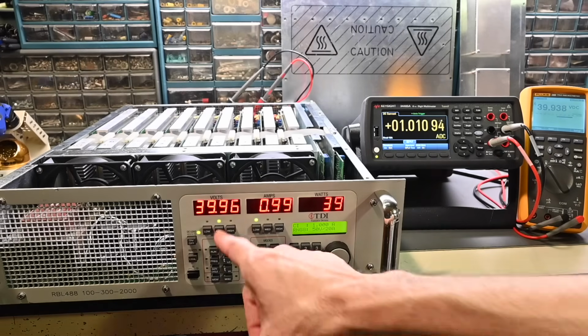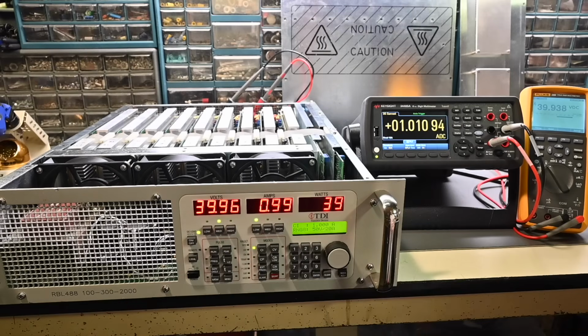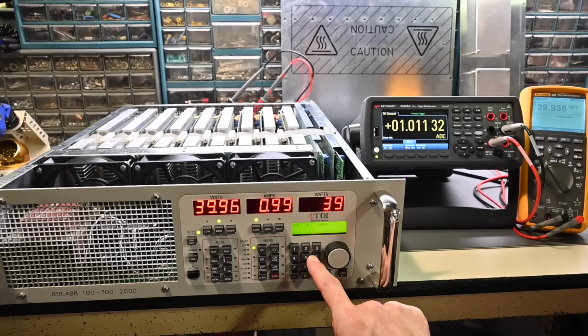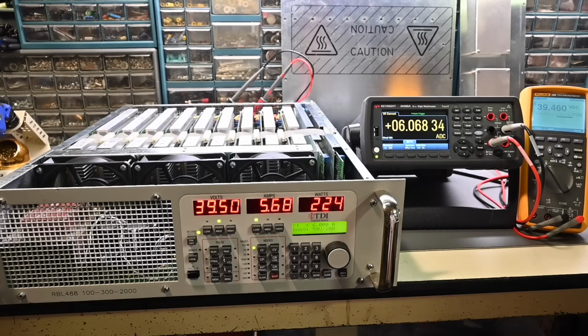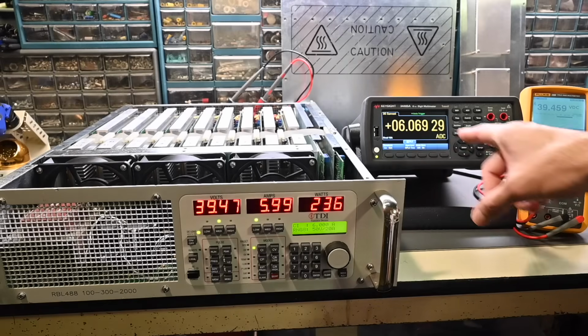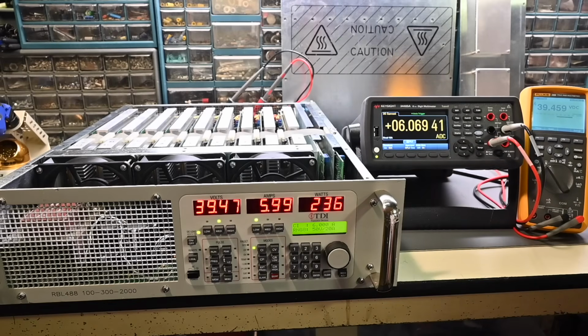Now, this was 40 volts. It dropped just a little bit because, again, there's some loss in the test leads and the cables. So that's to be expected. So 39.96, 39.93, very, very close. I don't see any problems there. That's fine. So yeah, that looks good. The numbers match up. So if I go a little bit higher, let's go back here, current, oh, let's try 6 amps. So a little more of a drop there, but 6 amps, perfect. And the voltage is matching there, 6 amps, great. So everything's looking very good.